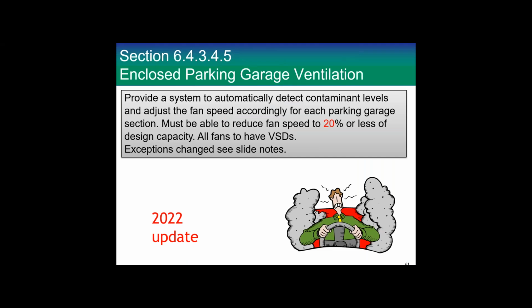Enclosed parking garage ventilation. We regulate parking garage ventilation because the building code says you have to put in fans with a certain amount of CFM per automobile, et cetera. And that's a big number, and it uses a lot of energy. That might be needed when all the cars are coming in the morning or all the cars are leaving in the evening. But for a long part of the day, you don't need those fans because nobody's running their car around in there, or very few people. So we provide a system to automatically detect contaminant levels, whether for gas vehicles or otherwise, and adjust the fan speed accordingly for each parking garage section.